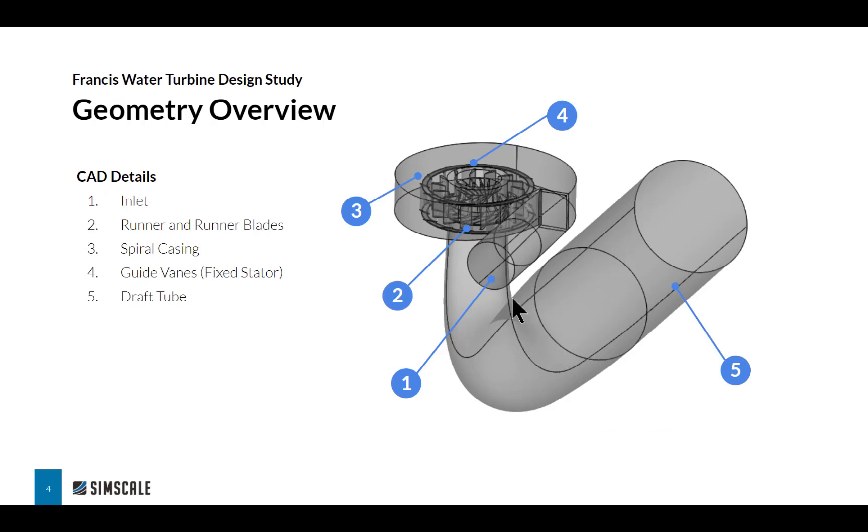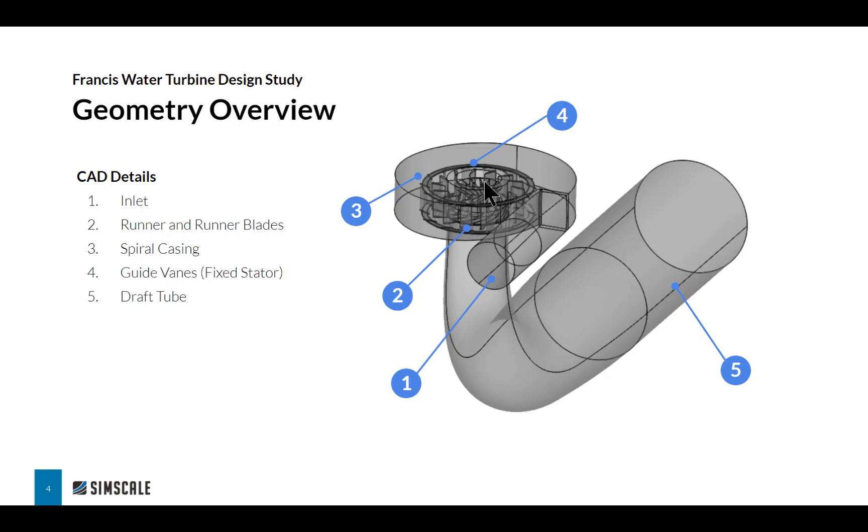The geometry is pretty straightforward. We have a simple inlet where water enters and is guided through the spiral casing, after which it rotates around and hits this first set of blades. These are known as the guide vanes and they guide the water into the next set of blades, the runners, which are the blades in the middle that actually rotate and generate the electricity.